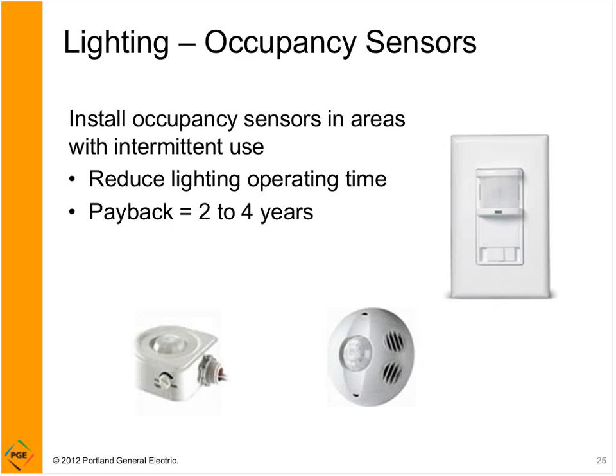Occupancy sensors can be a good opportunity if the space calls for it. You'd consider occupancy sensors in areas with intermittent use. So this might be individual offices or bathrooms, perhaps storage areas or a stock room in a retail business. The concept here is pretty straightforward. When there's no occupancy, no movement, lights turn off, so you're reducing the operating time of the lights. Payback is typically in the 2 to 4 year range for this improvement.